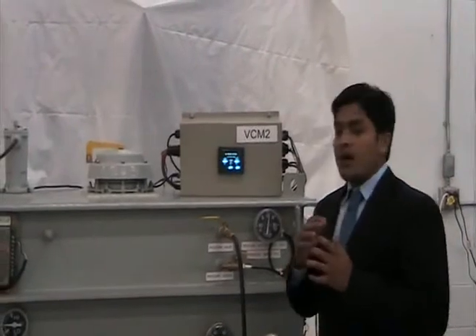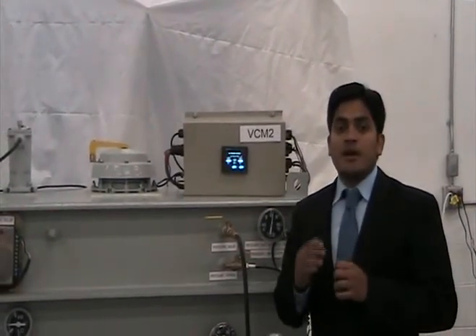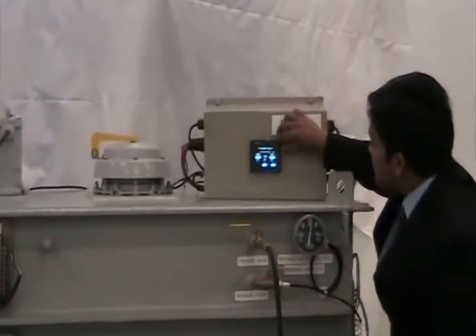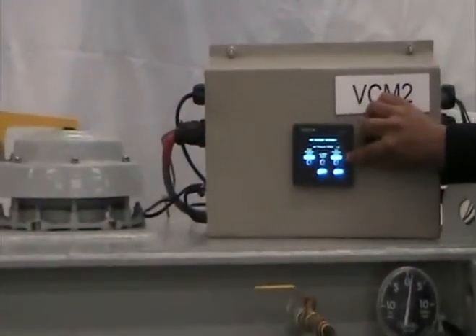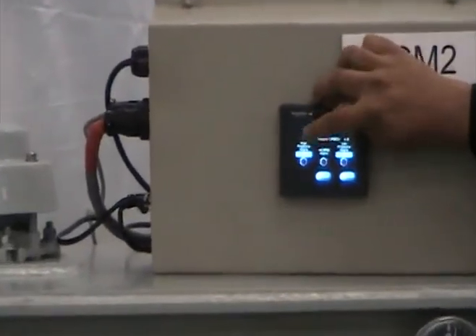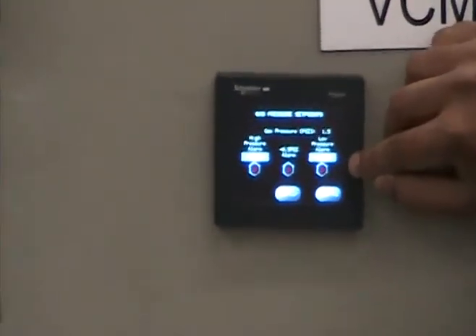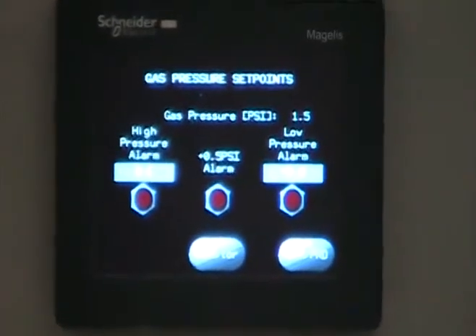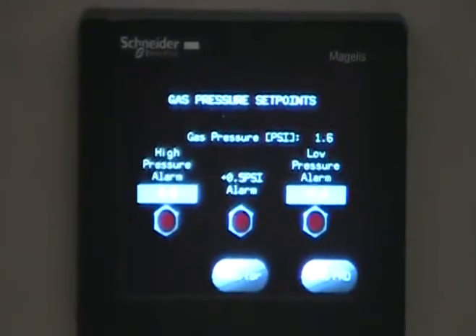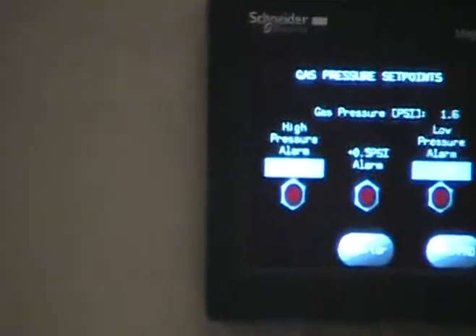One of the unique features of the VCM2 is the pressure monitoring. Now I will demonstrate how VCM2 can monitor the pressure. As you see, we have various set points for low pressure and high pressure. The low pressure set point is set at -7 psi and the high pressure alarm is set at 8 psi. You can see the gauge shows the reading as 1.5 psi and the VCM shows 1.5 psi. So both are same. Now I will simulate the pressure to more than 8 psi to activate the high pressure alarm.